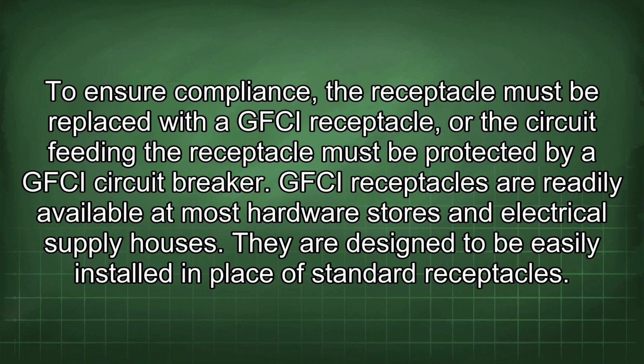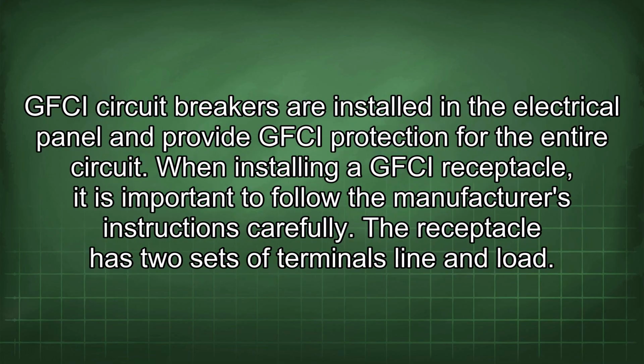To ensure compliance, the receptacle must be replaced with a GFCI receptacle, or the circuit feeding the receptacle must be protected by a GFCI circuit breaker. GFCI receptacles are readily available at most hardware stores and electrical supply houses. They are designed to be easily installed in place of standard receptacles. GFCI circuit breakers are installed in the electrical panel and provide GFCI protection for the entire circuit.